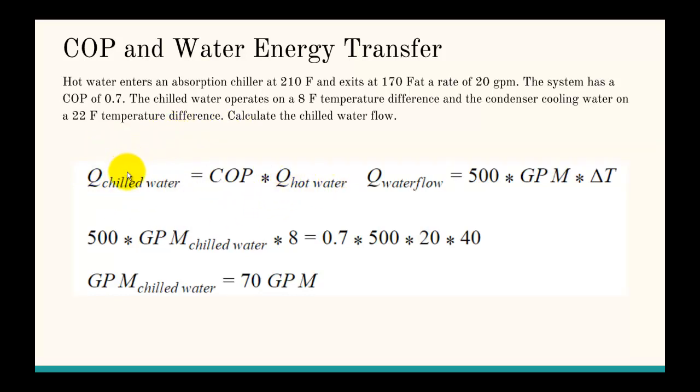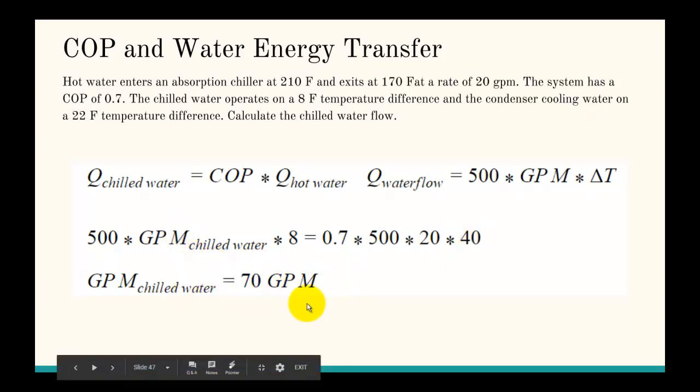What we do is take into account that any water flow has a heat flow of 500 times the GPM times the change in temperature. We set up this equation. On the left side, we get 500, and we don't know the GPM of the chilled water, so we keep that, and we multiply the 8 degree temperature difference of the chilled water. On this side, we take the COP, which is 0.7, then we take 500 times the GPM of the hot water, times the 40 degree temperature difference of the hot water. When we solve for the chilled water GPM, it's 70. And that's how we do that problem. Thanks for watching.